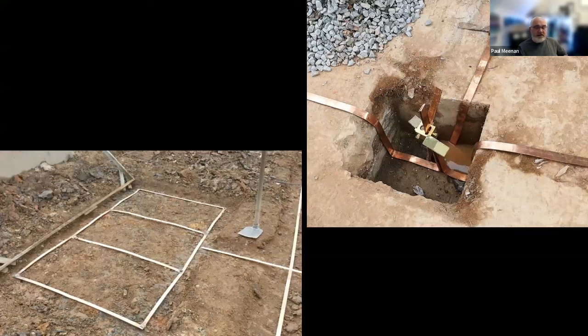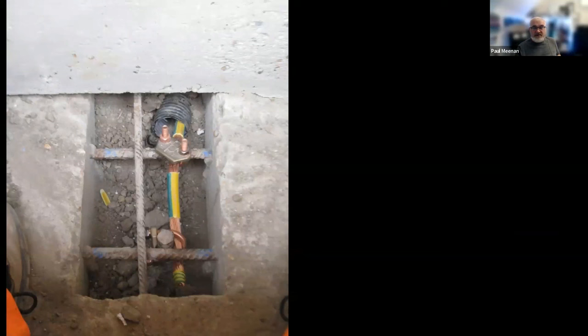Some good practices here in England. When we're building stuff, we use earth tapes, welded connections, and we create pits to create a large earth mat. They can also use rods as well. That gets covered up. We can also connect to rebar, so piling. That's a Crossrail transformer there. What we did was we put 28 meter piles in the ground, 150 of them, and connected the earthing conductor to the pile cap. And we got a fantastically robust, low impedance earth. So you can use structures and metalwork in the ground. You just make sure that you protect it from corrosion and you inspect it accordingly.